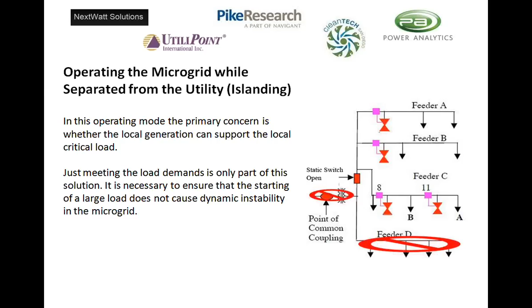So from an implementation challenges standpoint, what you have to really look at is the bifurcation of not only when I'm in a grid connected mode, but also in a separated mode, and all those transitions thereafter. There are a number of different issues to think about: various ones with voltage, frequency, power quality, even current and power factor in general. This has everything to do with balance, and balancing your current appropriately with the grid in general to the extent practical, or if you're separated into different loads.